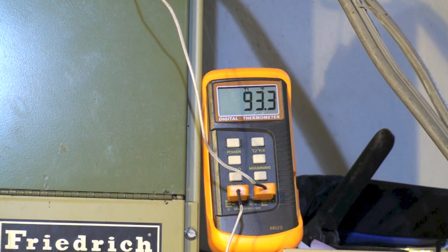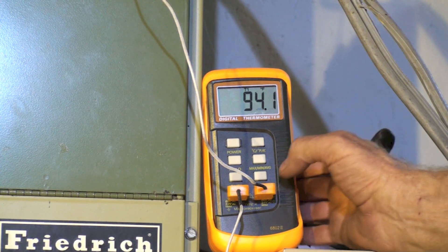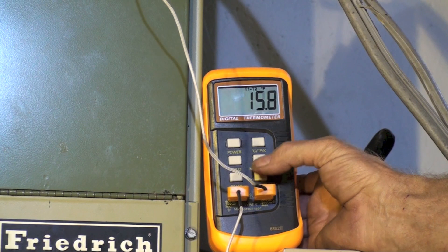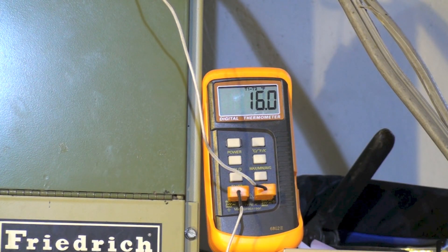The return air is coming back at 93, that's also the ambient for the outdoor unit, and 79 coming in.